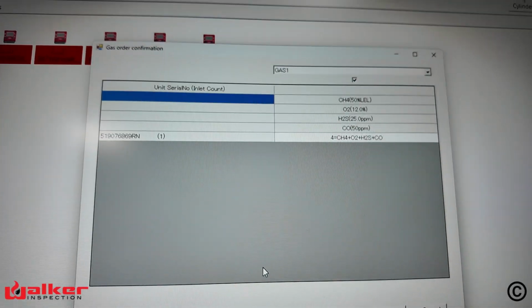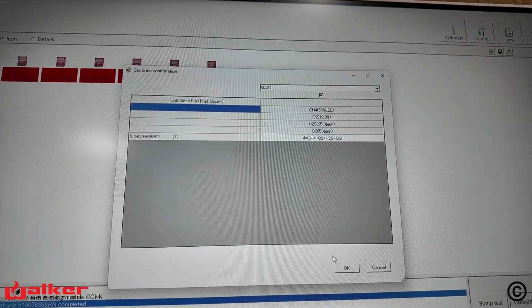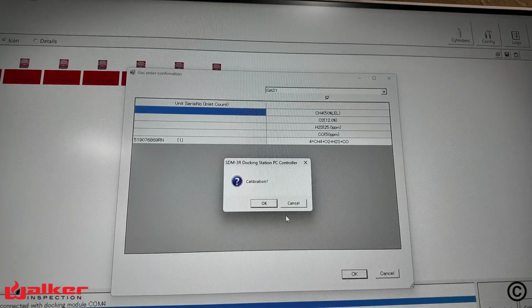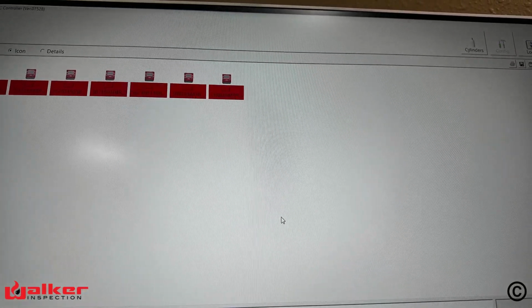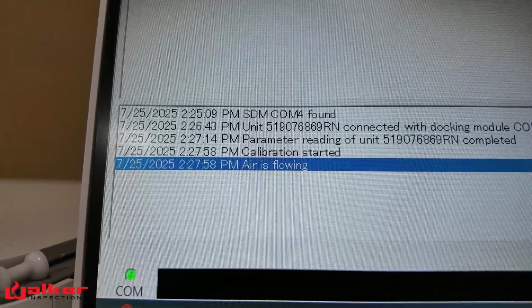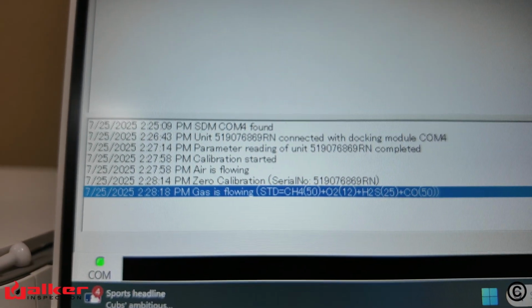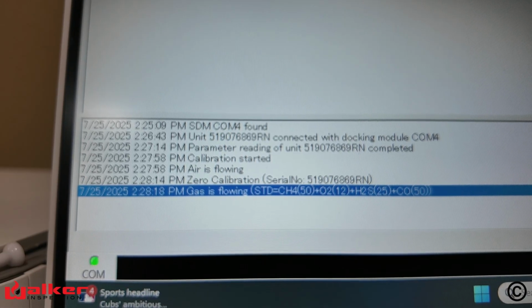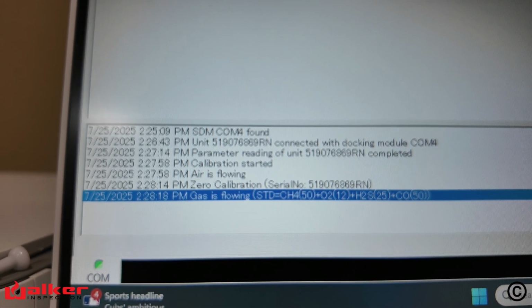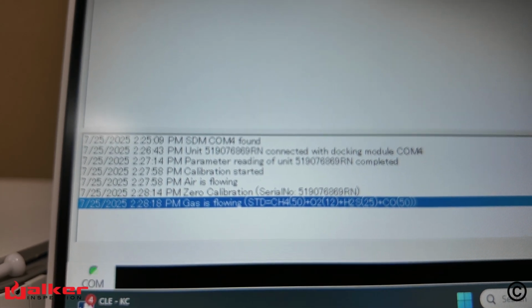It'll pop up a small browser with all of the different gases that it's going to test in the monitor, and you'll click OK. Then click OK on the next browser that shows the levels being tested. Then it's going to ask to calibrate and click OK to start calibration. From here, it's going to run all 4 of those gases to the monitor and test them. This will take a few minutes to complete.